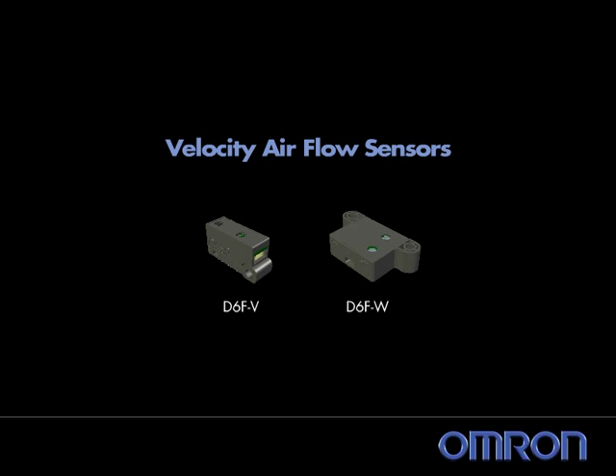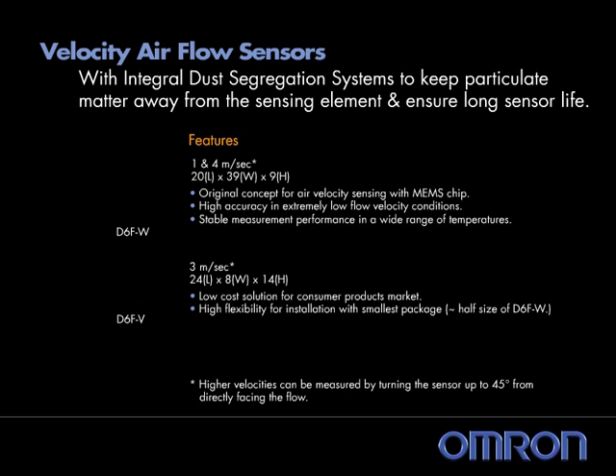In addition to the mass flow sensor products, OMRON has two velocity sensors that operate by the same principle. However, these sensors are meant to be positioned in the flow path; their outputs are related to air velocities rather than volumetric rates because the cross-section of the area they are in is unknown. The D6FW, like the mass flow sensors, has an amplified temperature-compensated output signal. The economical D6FV has an amplified output but is not temperature compensated, for cost-conscious applications with lower accuracy requirements.